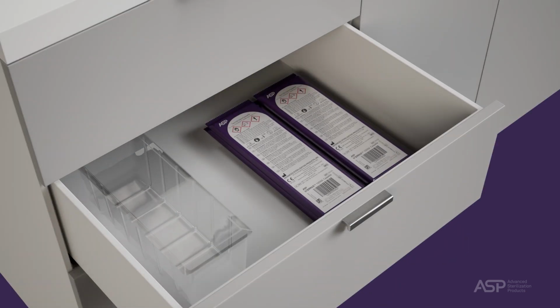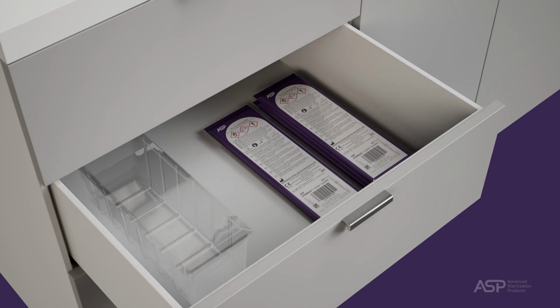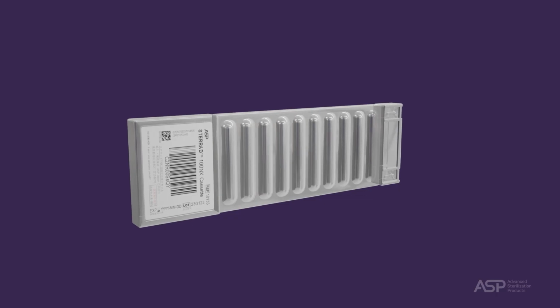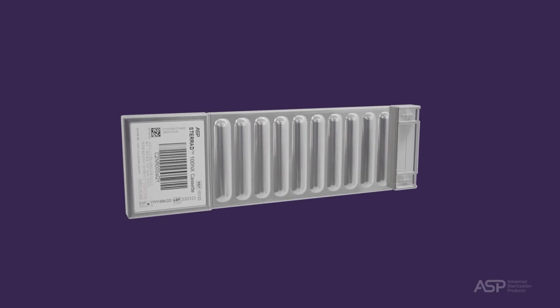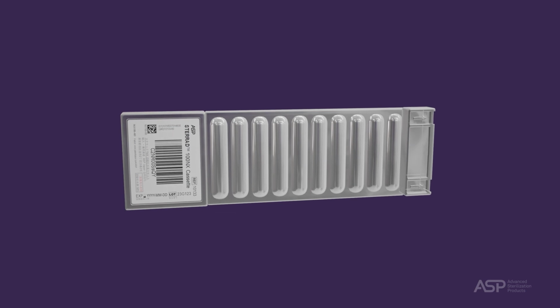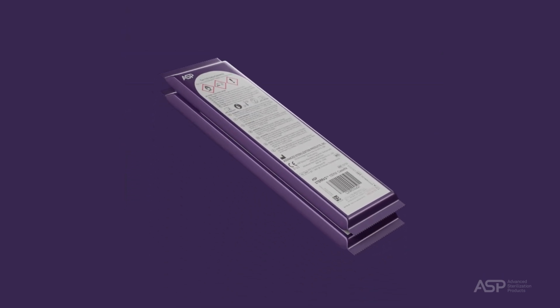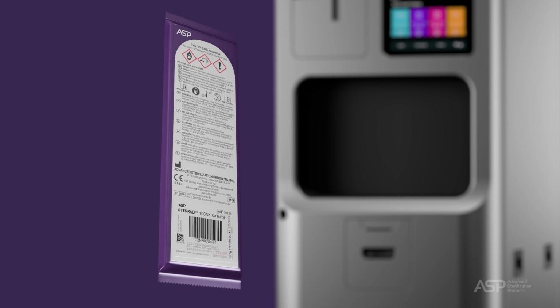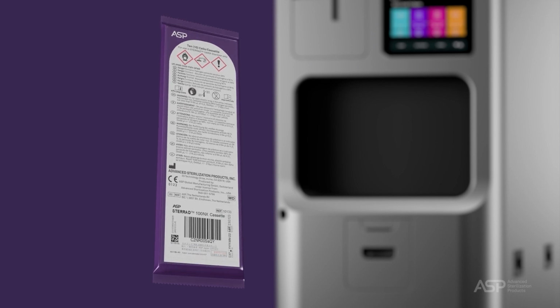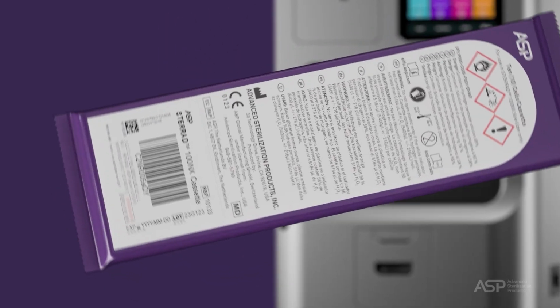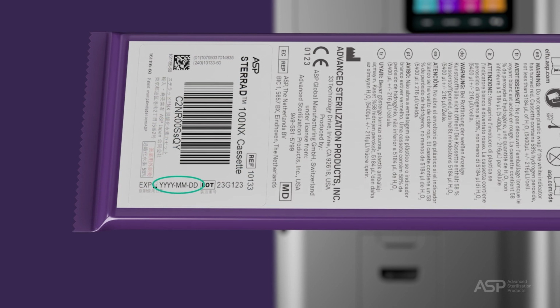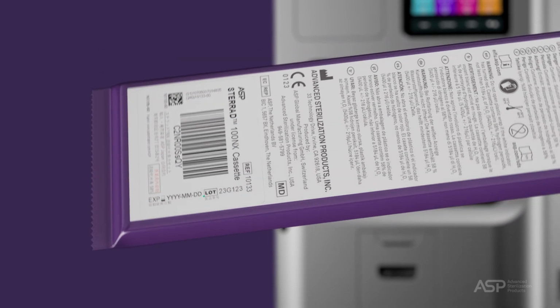To insert a new cassette, first, take a new cassette out of the carton. Each cassette contains 10 sealed capsules of around 58% aqueous hydrogen peroxide solution. There are 2 cassettes per case. Once the cassette is removed from the case, examine the packaging carefully before opening it. Check the expiration date. If the cassette is expired, do not use it.